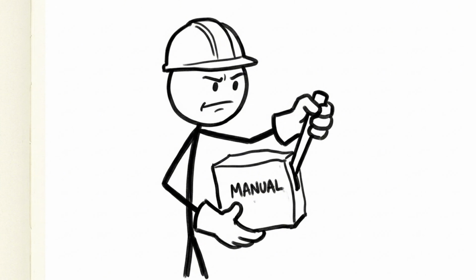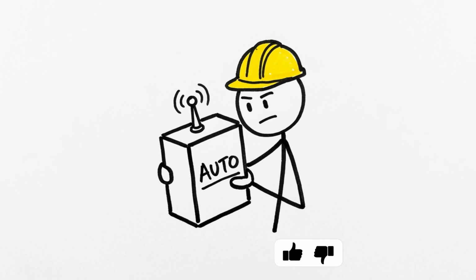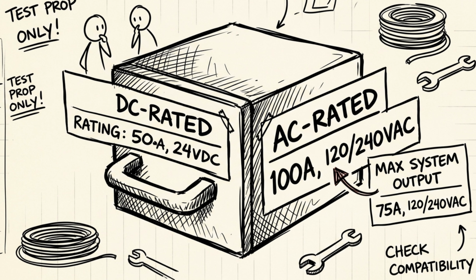The transfer switch itself comes in 2 flavors. A manual switch means you physically choose which loads run, and you carry the responsibility of not turning on more than the inverter can handle at once. An automatic switch senses grid loss and switches on its own, but it must either be sized for the full connected load or paired with a load management system that actively sheds circuits to stay under a safe ceiling. The spec that matters when buying either one: it must be explicitly rated for the type of power it's switching, DC-rated hardware for DC components, AC-rated hardware for AC components, and its voltage and amperage rating must exceed the maximum your system can ever produce.